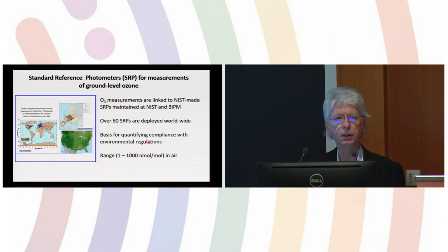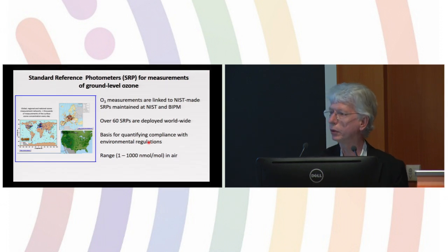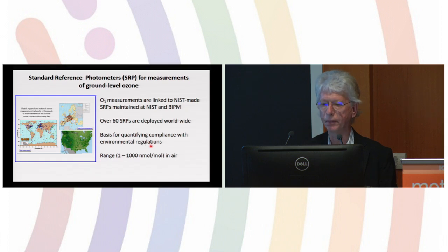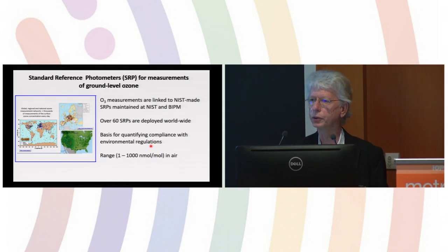It's based on observations of path length, number density, and an absorption cross-section, which is a molecular property or an invariant of the analyte. These are widely disseminated. There are four of them I believe at BIPM. This is the standard for ozone measurements, the SI traceable standard, the primary method.